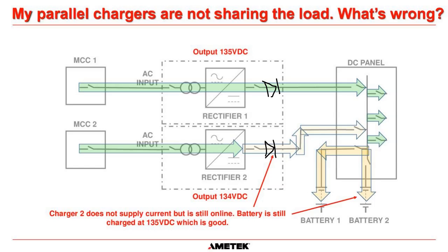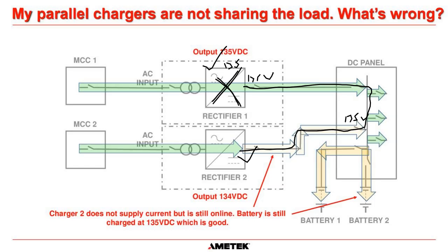The main reason for that, and we actually do this on our chargers as well, is we have to sense the voltage, and we have to sense especially if the voltage has failed. Now, let me just put this picture back up again. Let's say that this charger here, rectifier 1, has failed. Now remember, rectifier 2 is healthy, so we're going to get 135 volts at the DC bus from rectifier 2. And with that, all the way back to the charger terminals, we're going to get 135 volts DC. So even if rectifier 1 has failed, the sensing circuits inside rectifier 1 see 135 volts. So it actually thinks it's okay in some circumstances. Okay, that's not good.